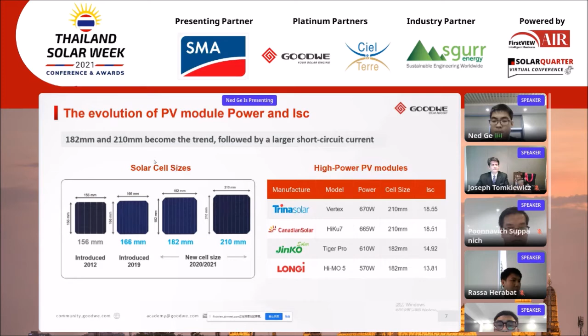Then let's take the Trina Vertex panel as an example. The maximum power current is 17.28 to 17.65 ampere. If used in bifacial condition, the current may reach even larger. So our KN series inverter can fully make the most yield of your 210 module, with a 20 ampere input current to cover the short circuit current.